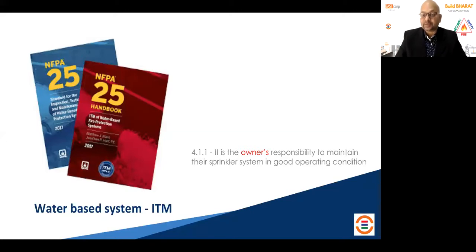During your commissioning, testing, or installation stage, you fit that cap, but the moment you take over the system you must remove the cap. If you don't remove it, the sprinkler will not activate, it will not come into operation. It is a dead fish, like a dead sprinkler. Although you have a sprinkler system, it will not come into play because of the cap.